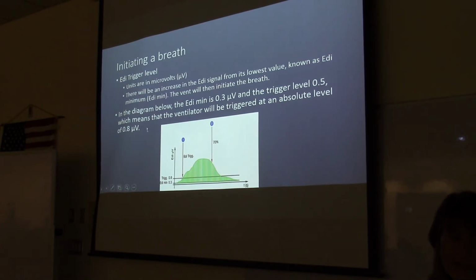So here it says in the diagram below, the EDI min is 0.3 microvolts. Do you see it down here? It says 0.3. That's the normal background noise, or it's called EDI min. The trigger level is 0.5, which means that the ventilator will be triggered to assist the breath at 0.8 microvolts. So far, so good? Mm-hmm.